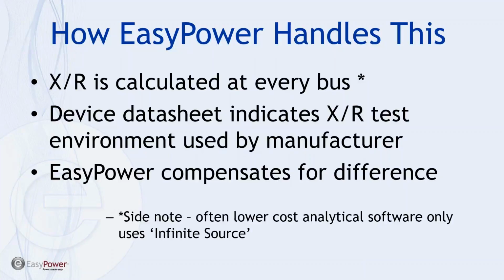So all these measurements are being made from the point of the fault back to the source of the energy, the source of the power. And in most cases, that is primarily a utility. And as I mentioned, some pieces of software only deal with an infinite source, and consequently there's some inadequacy or differences between the comparisons that are being made.